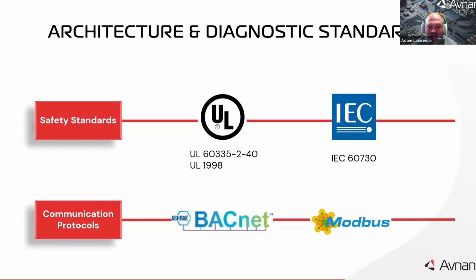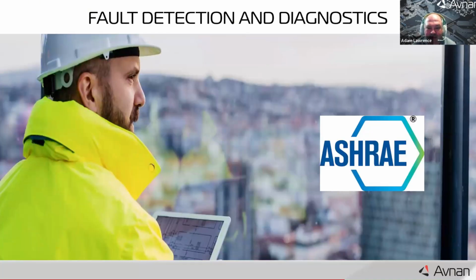We've also already talked a little bit about BACnet. Using BACnet's standard objects for sensors, alarms, and faults means that when your unit is connected to a building management system, it can broadcast its status in a way that the BMS natively understands. The data is clear and unambiguous. ASHRAE has a committee on fault detection and diagnostics. The industry is moving toward some level of standardization in how faults are named and categorized for analytics purposes. For example, ASHRAE's Guideline 36 for high-performance sequences of operation touches on standardized alarms for HVAC control sequences. Keeping an eye on these can help you align your fault taxonomy with what may become an industry norm.